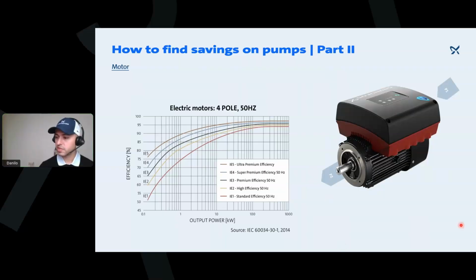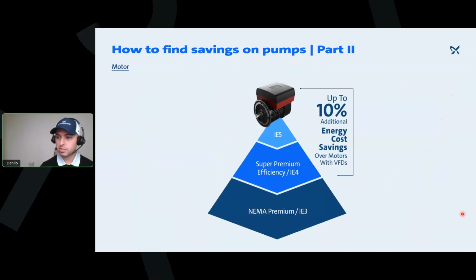On top of that, what I want to show here is just a comparison. By just utilizing an IE5 motor, you can save about 7 to 10% on energy cost, even compared with this motor. And again, I'm not just comparing this motor, which automatically has a VFD, but we're also comparing this other super premium motor with a VFD, right? So just by utilizing these motors with the VFD compared to the permanent magnet motor, you already have 7 to 10% energy savings.